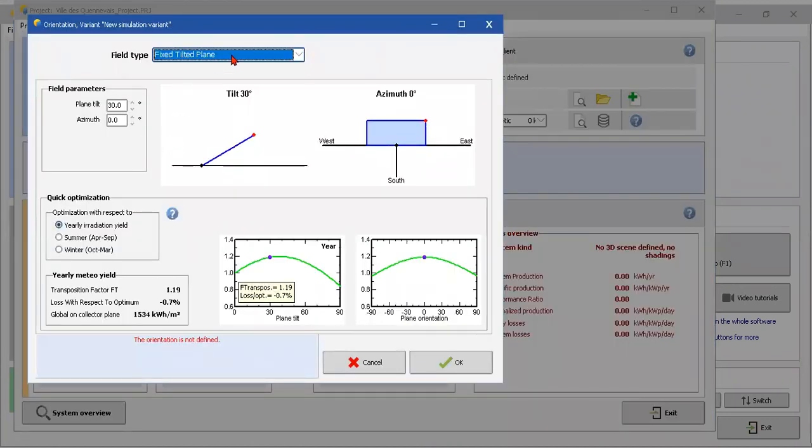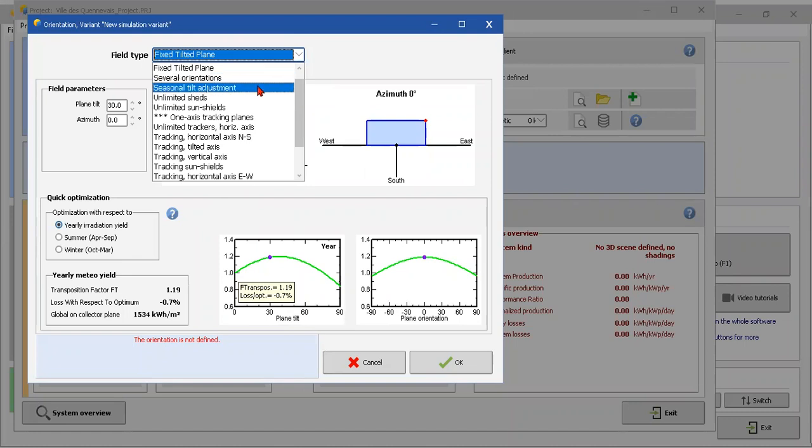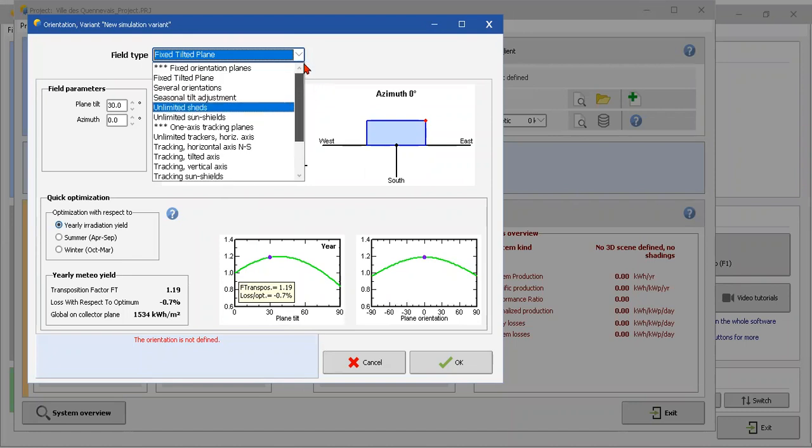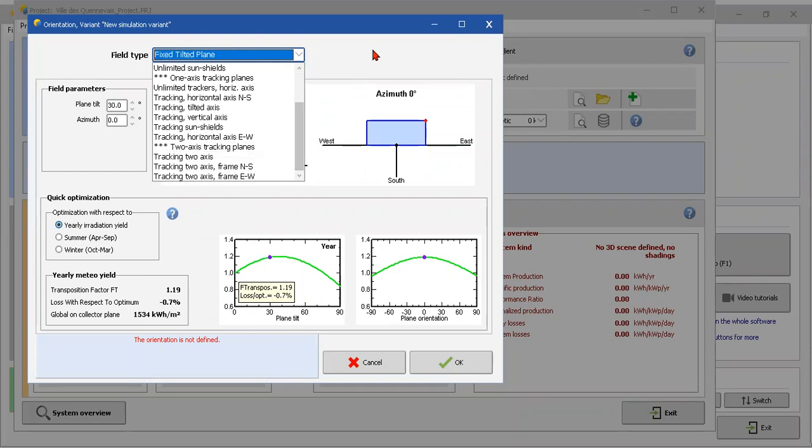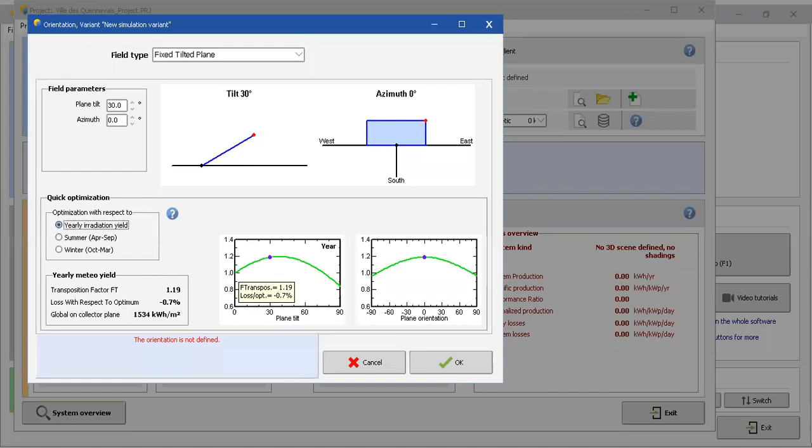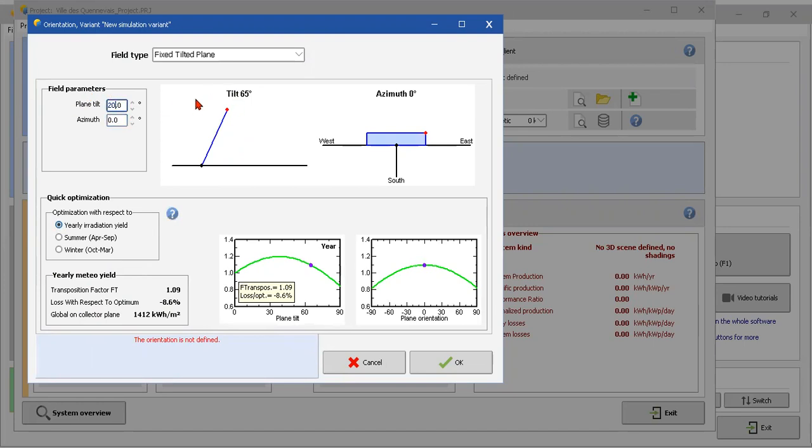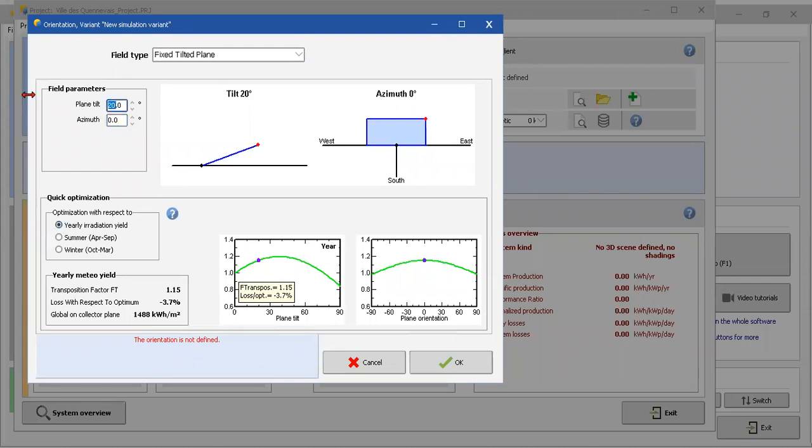Yes, the synthetic array - we have to save. Yes, well, that is in yellow in the product, it's like a recommendation. If it's in red, it's because something is wrong. So save the sheet. We're gonna save it, for example, here. It's red because we didn't do this, so we're gonna do now - Orientation. So here, field type, several orientations: seasonal, or just one. A lot. Just with fixed tilt plane. So we have the tilt here and the azimuth here. And the optimization with respect to yearly, summer, winter. This is on-grid, so we're gonna choose yearly.